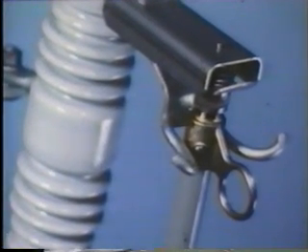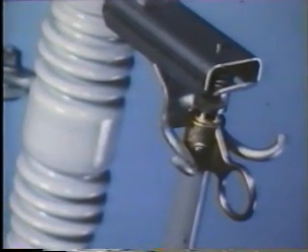Each cutout includes standard load break hooks to use with portable load break tools. This method is particularly useful for switching of the 200 ampere fuse holder and 300 ampere disconnect blade. However, with the Chance Link Break Cutout, the fuse tube does the interrupting job — a much safer method.